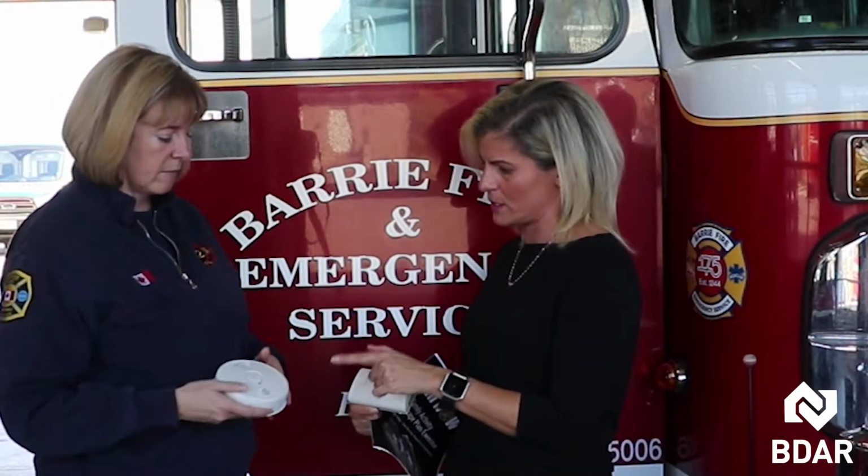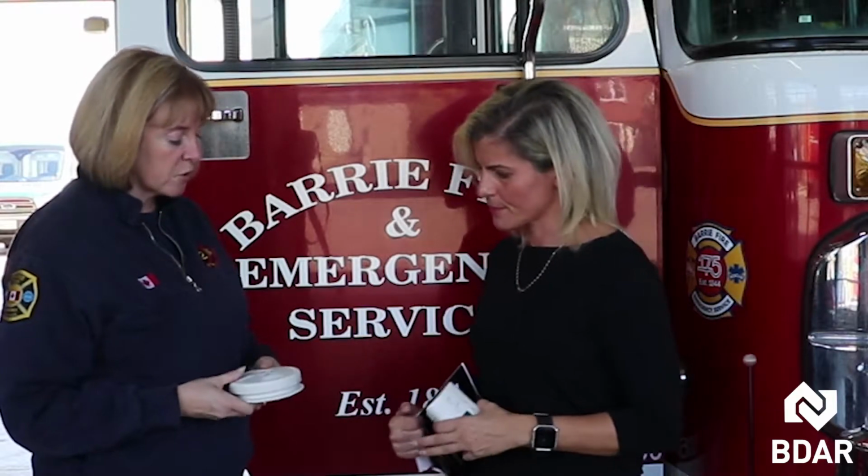And so the same with the smoke detector. Yes, the smoke alarms are the same. So with a smoke alarm, when you're looking at people's houses, you'll get pretty good at seeing how old they are without even checking the date. But you should know, and your realtors should know, that in 2006, they passed a law that said all alarms have to have a replace by date. So if you don't see a replace by date, right away you know it's too old. Then all you need to do is push and hold the button. Same thing. You've pushed the button, you've acknowledged that you're testing it, it's going to go through its process here, and it's going to let us know that it's working. But that way you know that it has power, it's going to provide the family with the early warning.